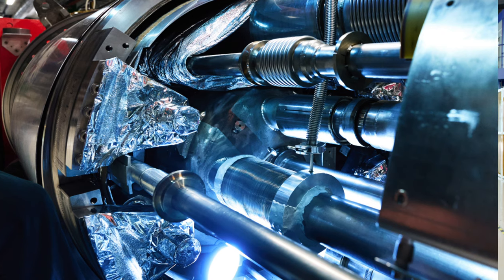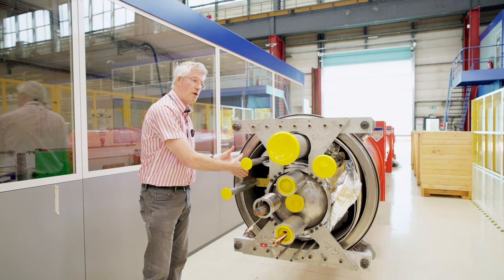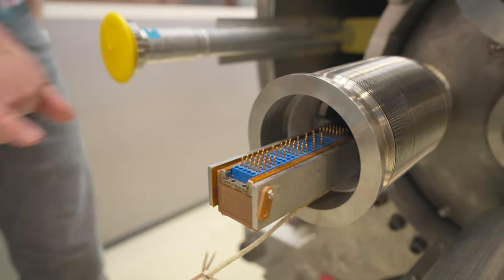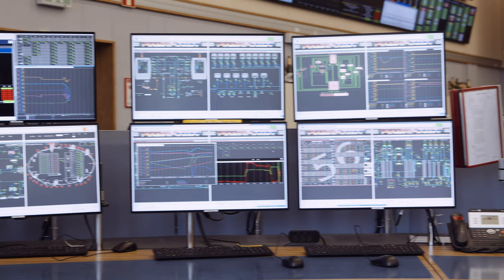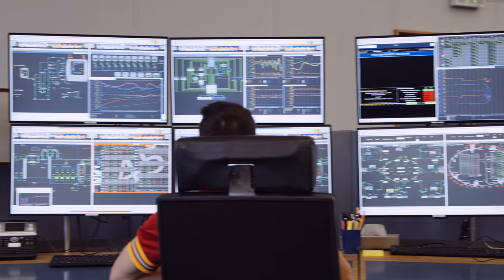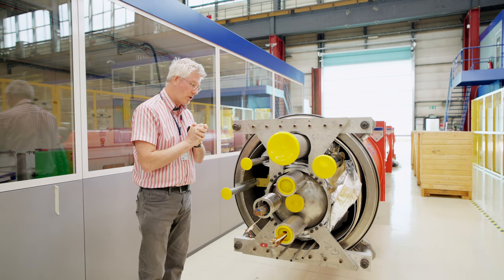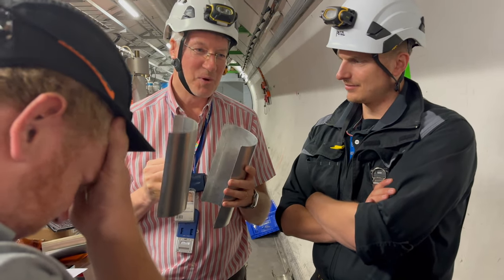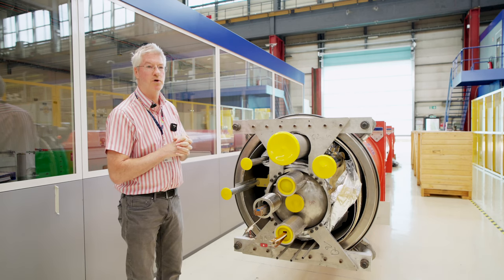We connect the leak detector and validate the leak test. This took a total of four days from when we identified the leak to recreating the vacuum — exactly four days. We were then able to cool down on the 1st of August, 2.5 weeks after the initial problem. Even though the proton physics program was interrupted, we've minimized the effect on the physics program for CERN, and hopefully we will be cold and in operation in about three to four weeks.